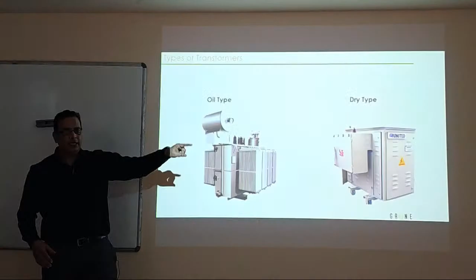But you need to understand metering strategies, because when you design a building, there are various meterings, and that's where your rooms come into the picture. What rooms are needed where? Basically we define three metering strategies: high tension metering, low tension metering, and a combination of high tension and low tension metering. If I was doing a simple residential building, I would design the property for LT metering, low tension. That means I have small meters in an electrical room.